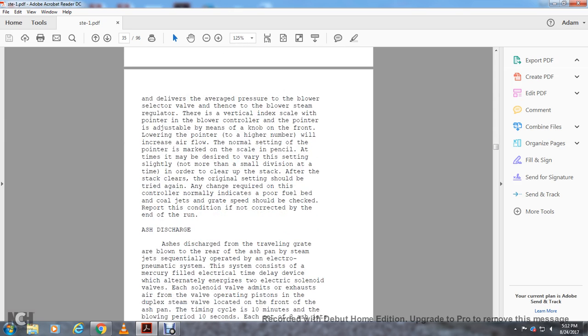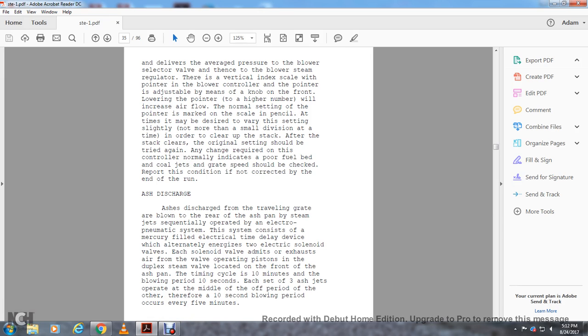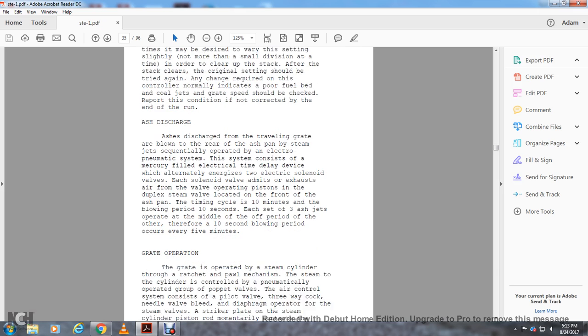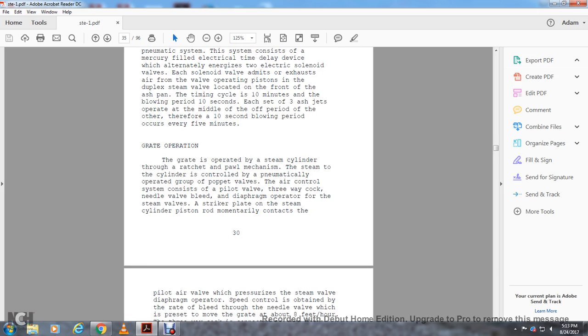Ash discharge. Ash from the traveling grate is blown to the rear of the ash pan with steam jets, sequentially operated with an electro-pneumatic system. The system consists of a mercury-filled electrical time delay device, alternately energizing two electrical solenoid valves. Each of the solenoid valves admits and exhausts air to the valve operating pistons in the duplex steam valve located on the front of the ash pan. The time cycle is 10 minutes and the blowing period is 10 seconds. Each set of 3 ash jets operates half a period after the other. Therefore, the 10-second blowing period occurs every 5 minutes.